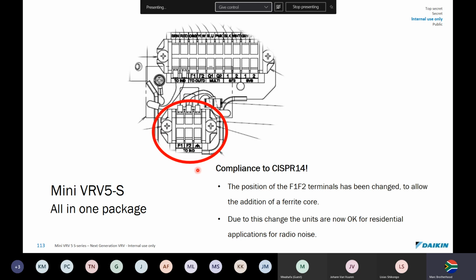And they've also changed the position of the F1, F2, which is obviously our communication network, to allow the addition of a ferrite core. What a ferrite core does is deal with harmonics coming into the system and any noise. That's probably the ferrite core at the back there. We take the cables through, and it acts like a big sponge, and it absorbs any of the interference and noise that is coming in from the building supply.